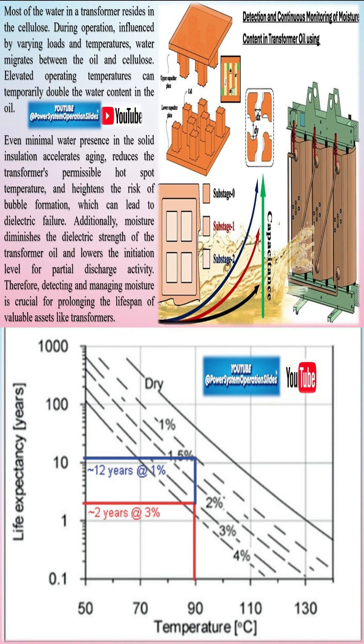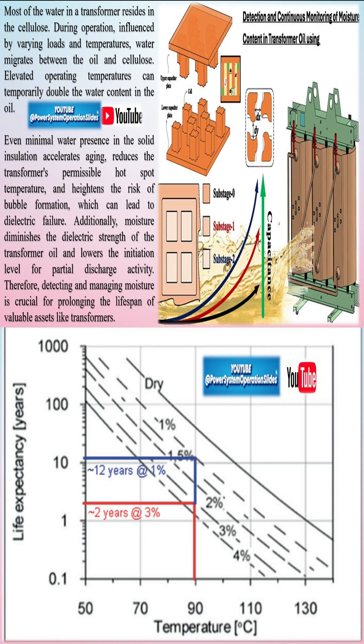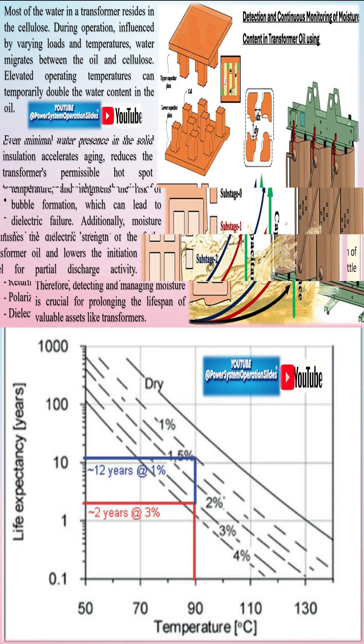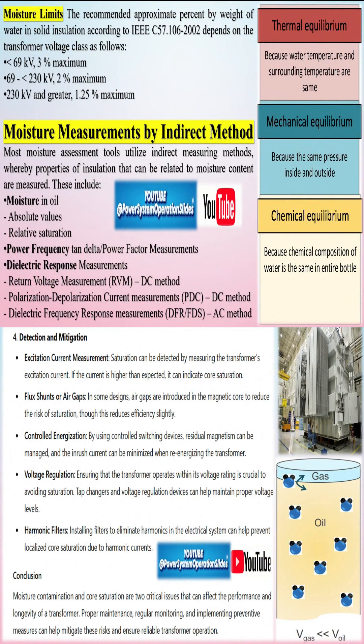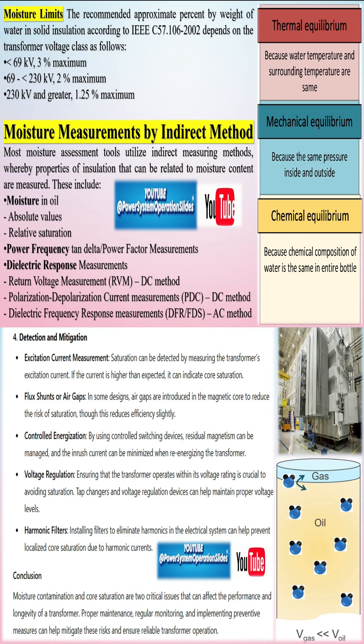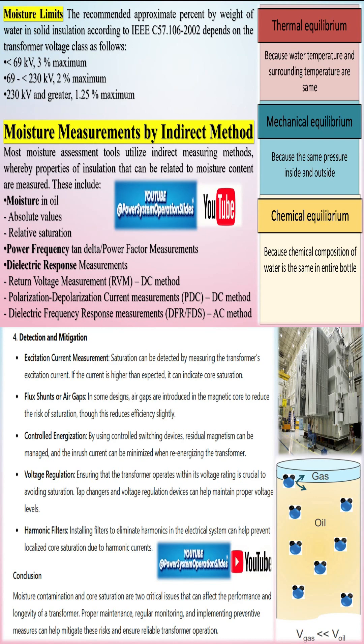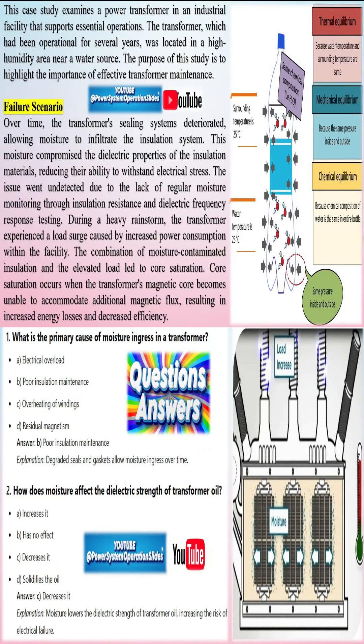Moisture contamination in a transformer is one of the most critical issues that can severely affect the transformer's performance, reliability, and lifespan. Power transformers rely on high-quality insulating materials, primarily transformer oil and cellulose-based paper, to maintain dielectric integrity. However, these materials are hygroscopic, meaning they have a strong affinity for absorbing moisture from the surrounding environment, leading to moisture contamination over time.